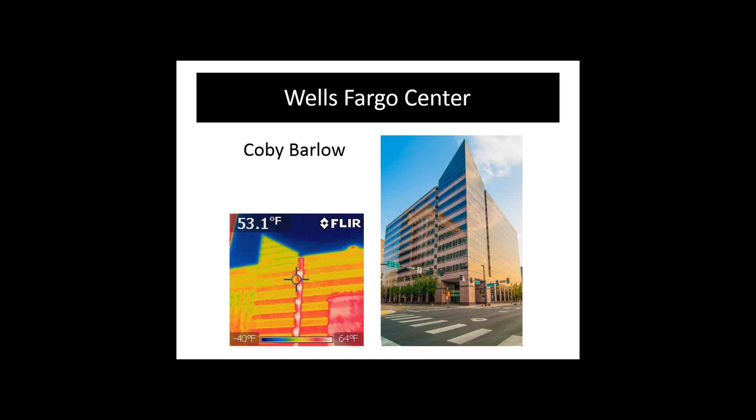was diving into this project. Then the building has 12 separate air handlers in it. And as we started looking into it, we found the air handlers don't have any chilled water control on them. It's 100% chilled water through it all the time. As you know, different floors have different loads, so you've got a floor with 120 people on it that you're trying to keep happy, so you crank your chilled water down really cold to keep them happy, and then you've got a partially loaded floor where you're giving them that same amount of cold water, so you've got one floor freezing and one floor that's hot.